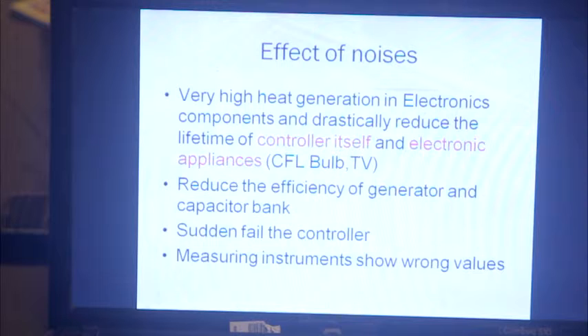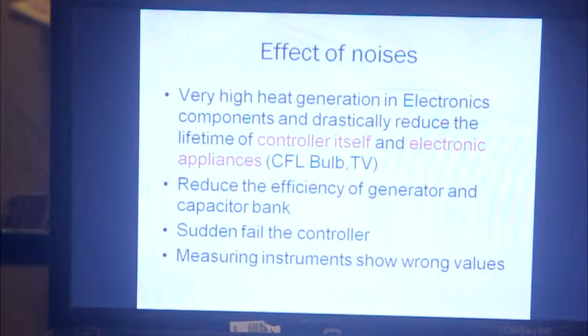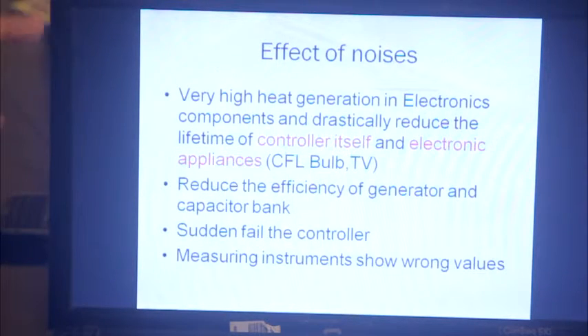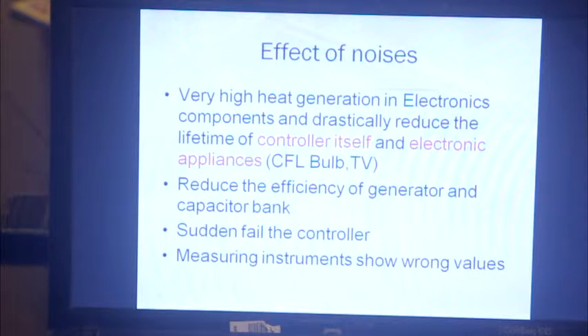All three types of controllers generate noise at different reasons, which badly affects the hydropower controller itself and other appliances in the system. Most controllers suddenly fail within one or two months due to this noise. This also badly affects CFL bulbs with electronic circuits and TVs and radios, whose lifetimes are drastically reduced. Generator efficiency is reduced, and the lifetime of the capacitor bank on the induction generator is reduced. Additionally, most measuring instruments show wrong values when measuring voltage or current in the system.